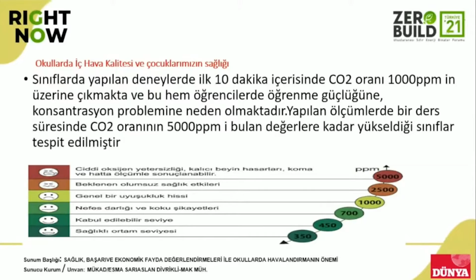So this high level of CO2 is problematic, and we should prevent it. And ventilation systems are important for our schools. So physical conditions in our schools, because in recent school buildings, one student has almost 1.3, 1.5 square meters. And in a classroom, which is 45 square meters, we have 30 students, and they spend 40 minutes in these classrooms. So the height of the classroom is 3 meters, and when we multiply 45 with 3, it is 135 cubic meters.